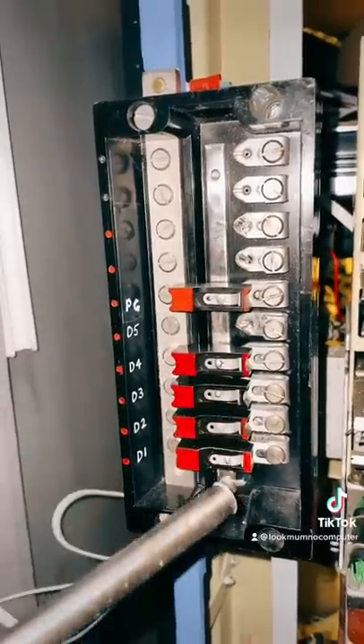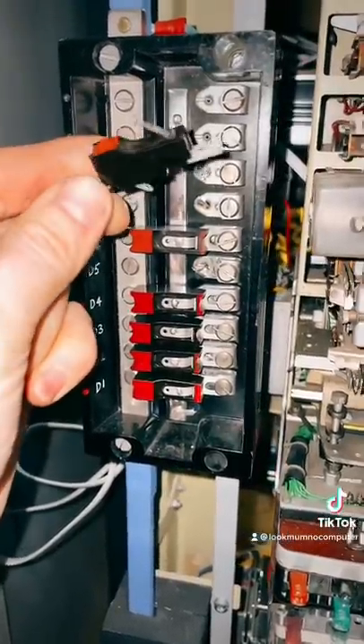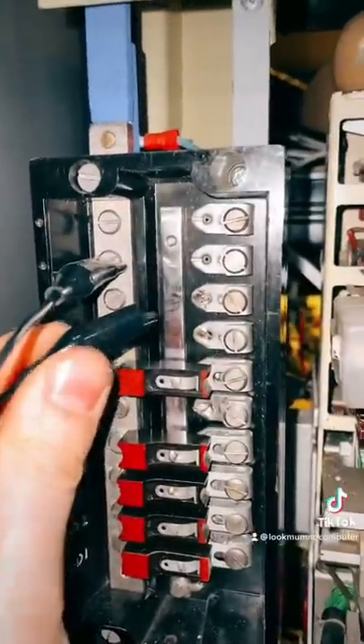In between is this metal contact, and that goes directly over to a buzzer. When the fuse breaks, it diverts the voltage over to that alarm bar, making the alarm go off. Let's touch the alarm bar and see what happens.